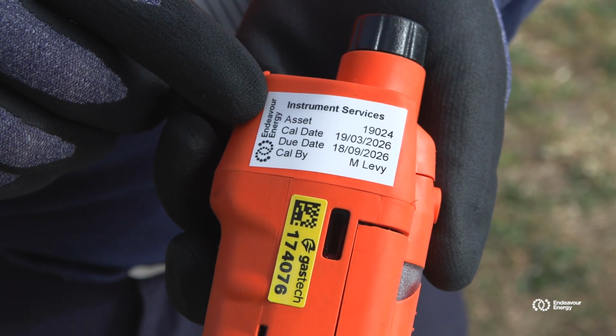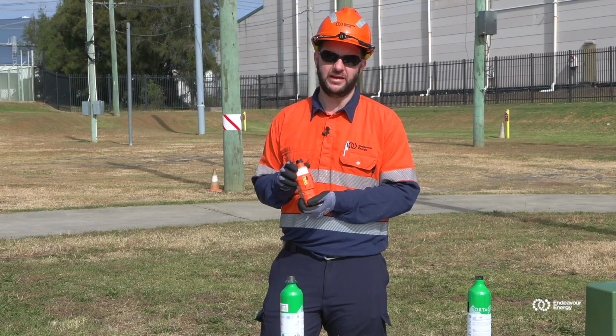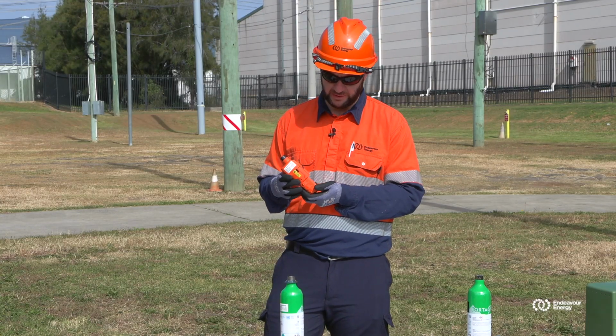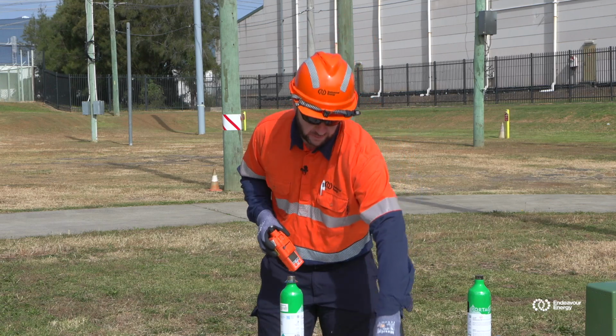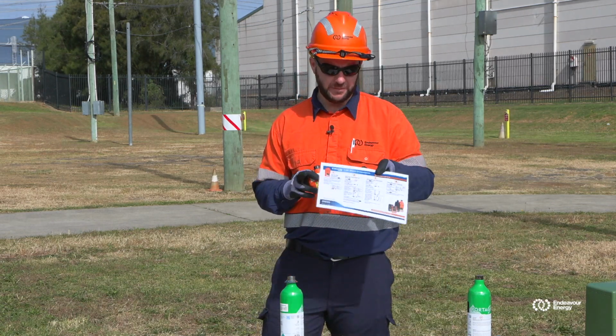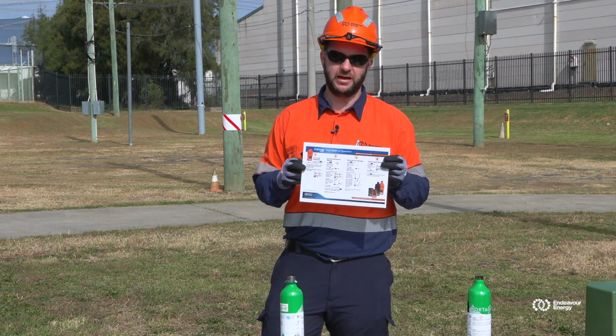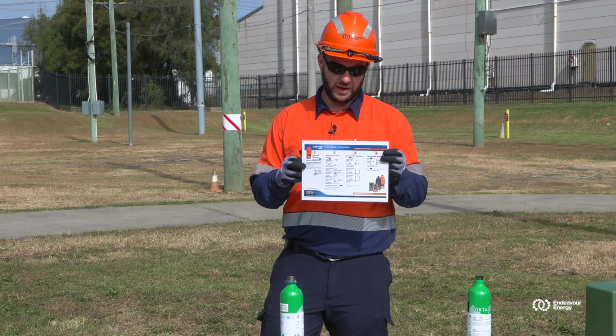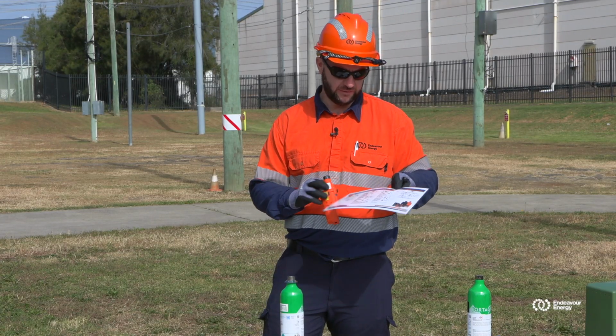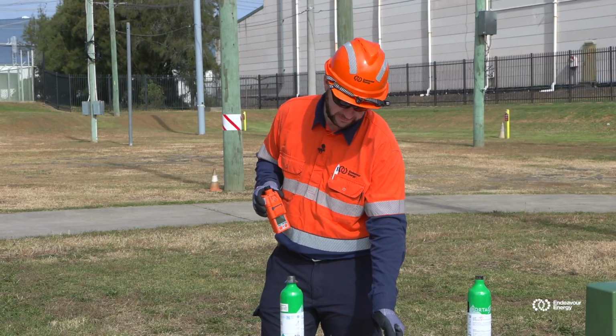If there's any issues, contact instruments, but the test dates will last for 6 months generally from when we get it. When using the unit, we also come with a quick reference chart, so we can refer back to that for any questions when we're using the unit. Otherwise, I'll go through today and I'll give you a demonstration on conducting a bump test.